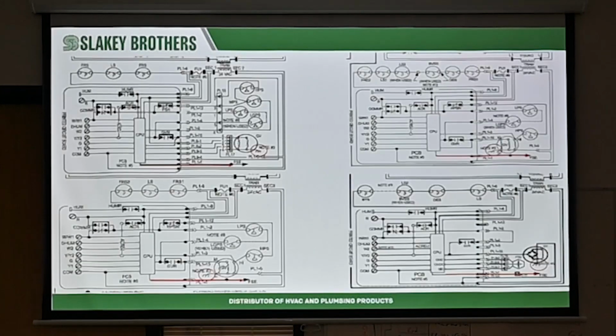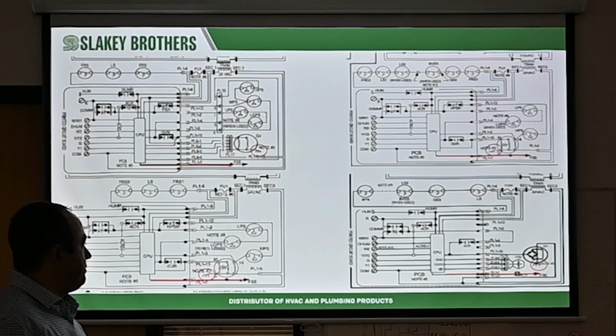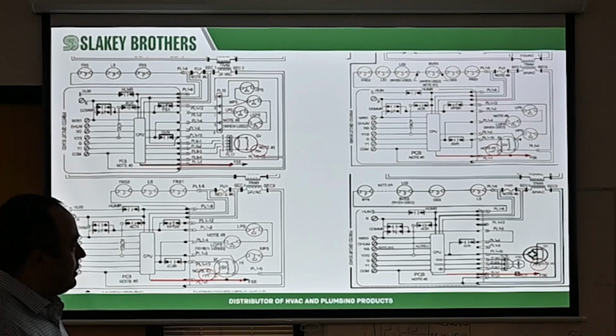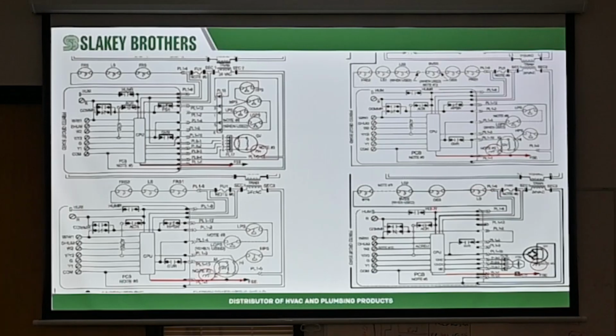So, okay, your electrical circuit over here. These are the 4 different types of systems that we have. Modulating, 2-stage, and so on. This is your modulating gas valve. This is your 2-stage. The other version of the 2-stage, and I think this is actually a single stage. This is for the unit you guys won't run across, that ultra low NOx furnace. But they all got a flame sensor that connects onto the CPU, to the computer. Again, all of the gas valves got to make sure that they're grounded.